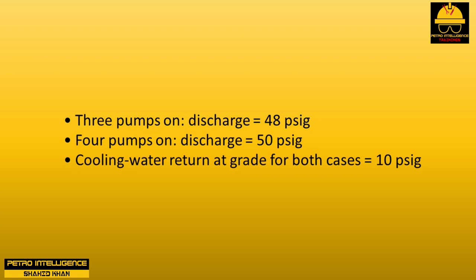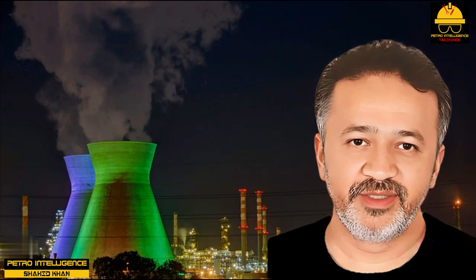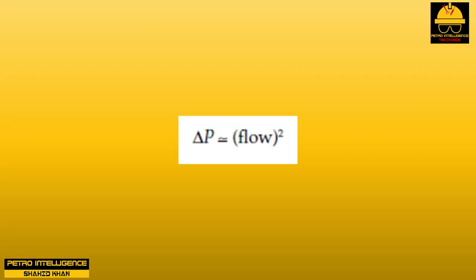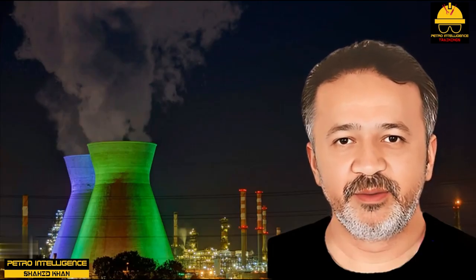For example: three pumps on discharge equals 48 psig; four pumps equals 50 psig. Cooling water return for both cases equals 10 psig. The delta P for the three-pump case is 38 psig; the four-pump case is 40 psig. That means the pressure drop through the exchangers and piping system has increased by 2 psi, or 5%. Since pressure drop varies with flow squared, the water flow has only increased by 2.5% by starting the fourth pump. This does not usually indicate a pump malfunction — more likely all four pumps are operating on the flat portion of their pump curve.